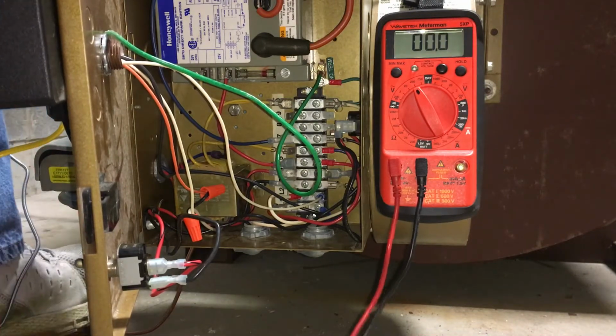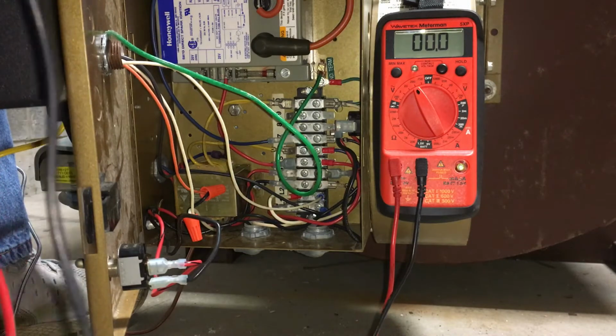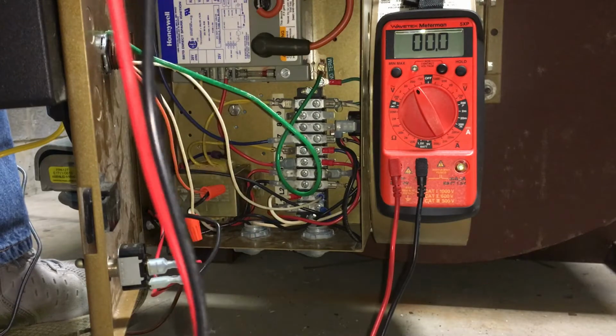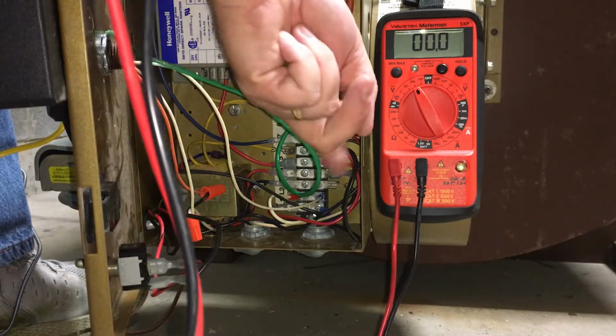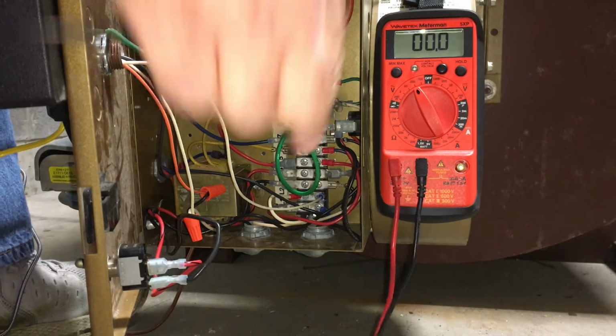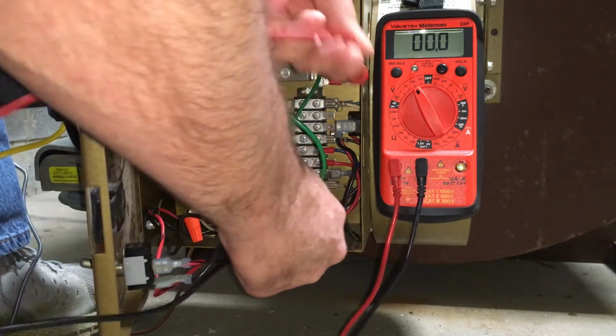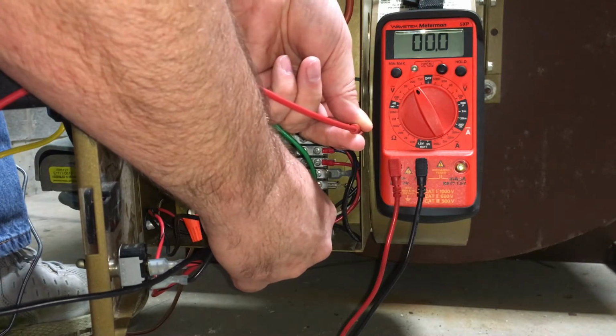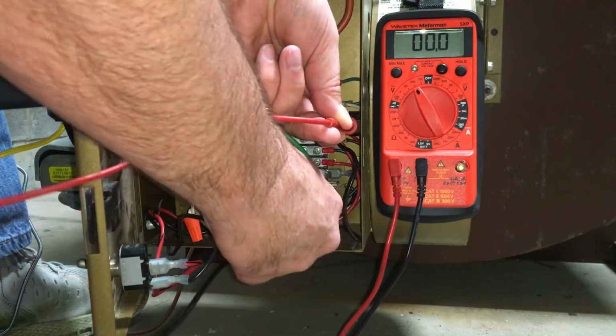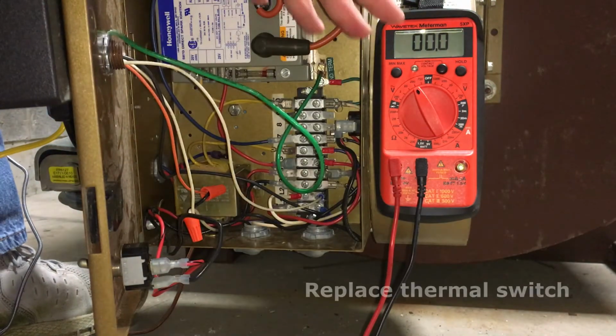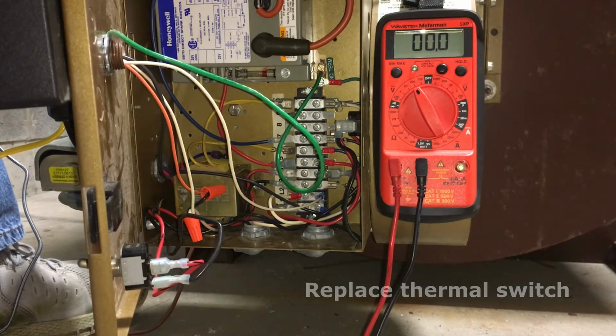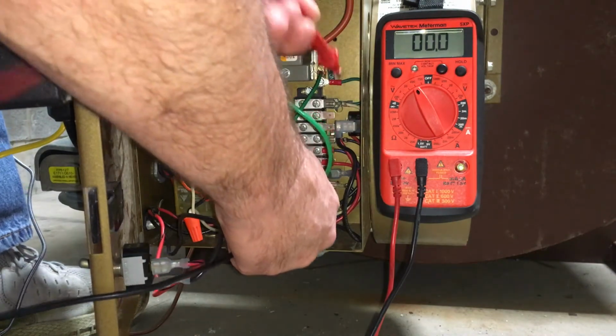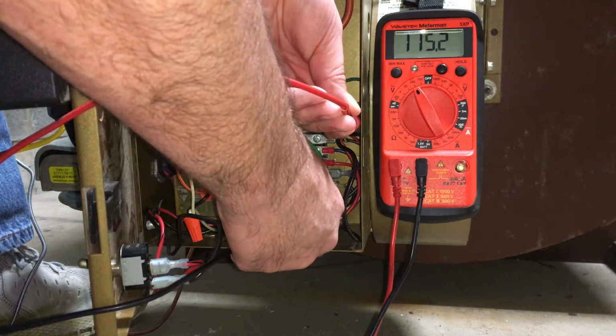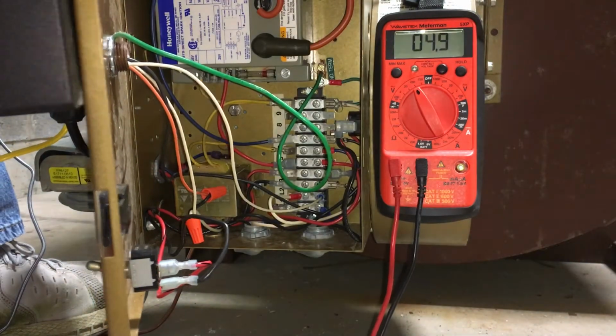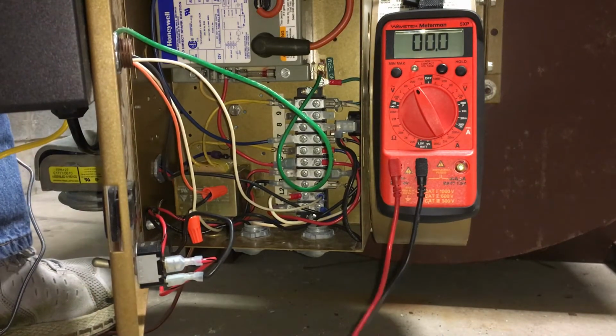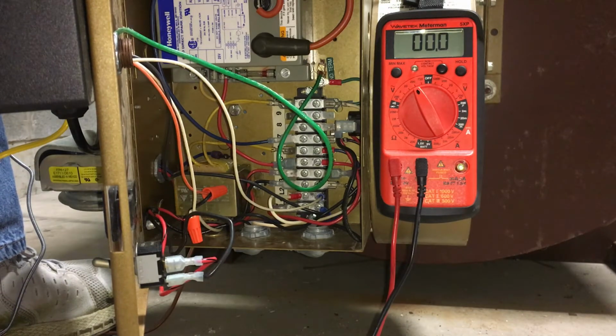The next step to verify that we're getting proper full voltage is L2 and the thermal switch, which is this switch here, the heat sensor switch, on terminal 1, which would be the black wire. So we would check between L2 and this terminal, and again, it doesn't show that we have anything running, doesn't have any voltage through it. So I will act as if that is the failed switch. We'll replace the switch. Check it again. There, we're getting proper voltage through it. So each of those steps indicates you're looking for full voltage of 115 volt through the system if the motor will not run.